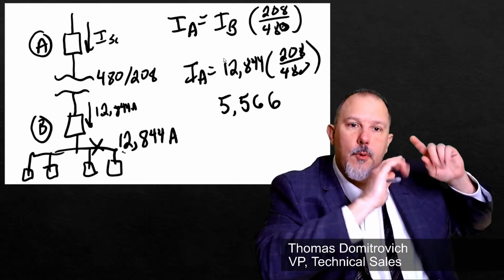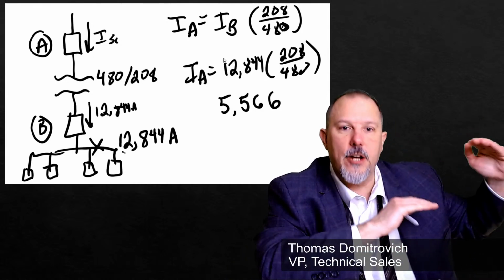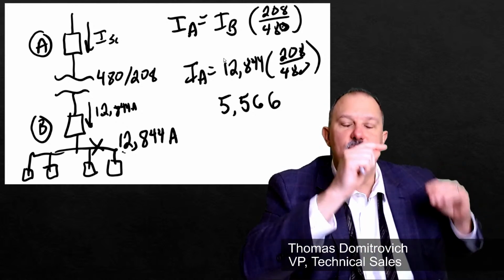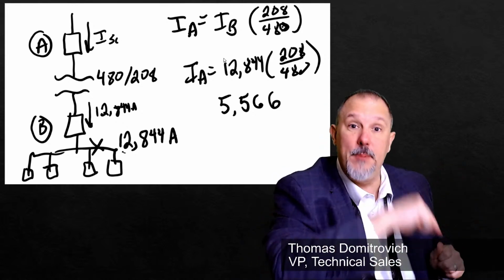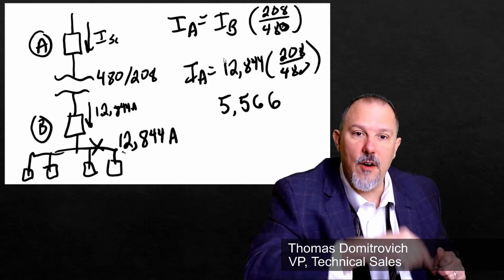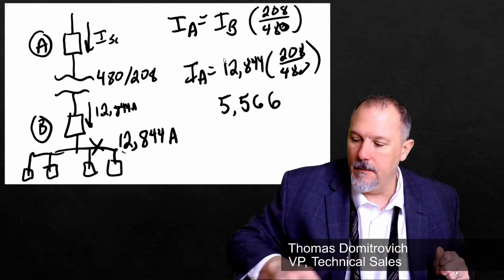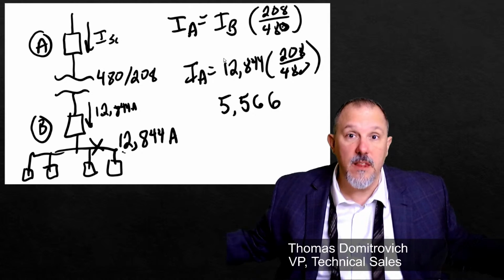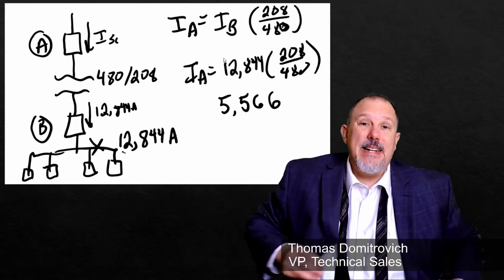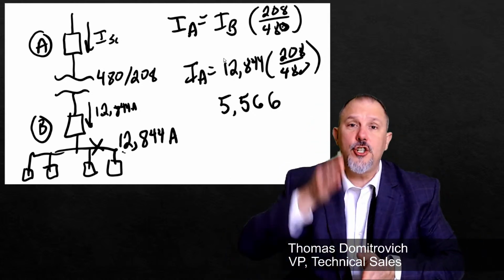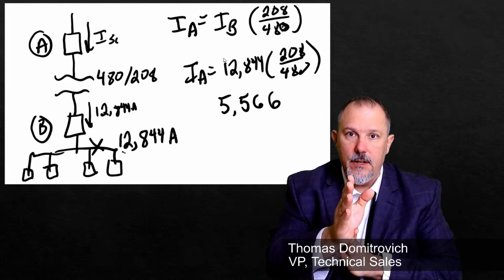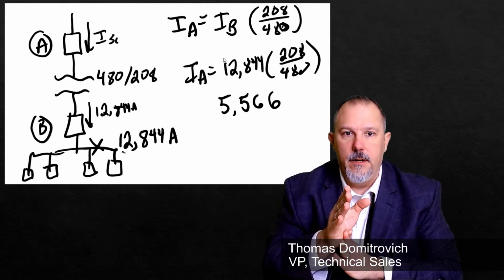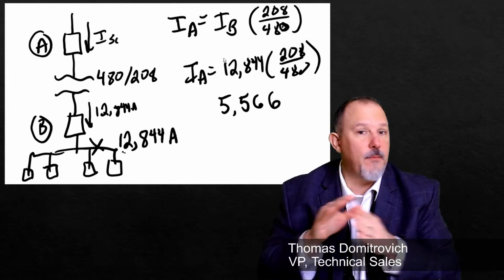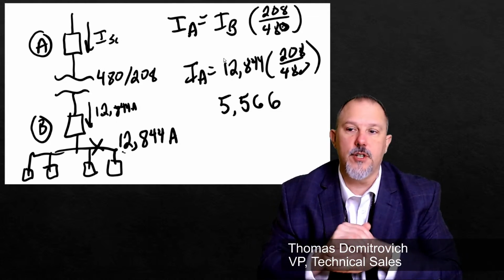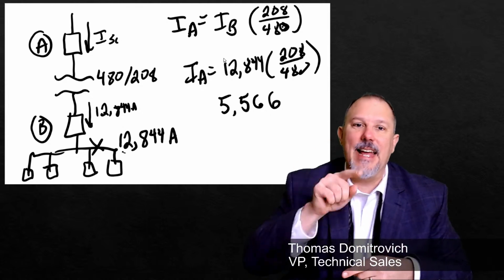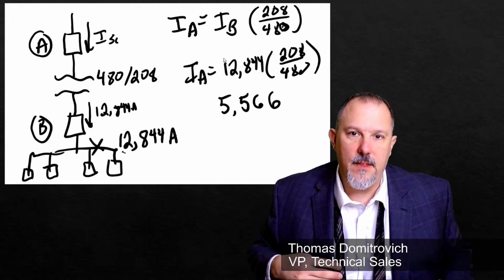The breaker A, the primary breaker on this transformer, is going to see 5,566, while breaker B is going to see 12,844. How do I use the tables in this situation? Remember, my tables are made by shooting current through two devices at the same current. In this case, I don't have the same current going through both of those breakers. So my question to you is, can I use the tables in this method?